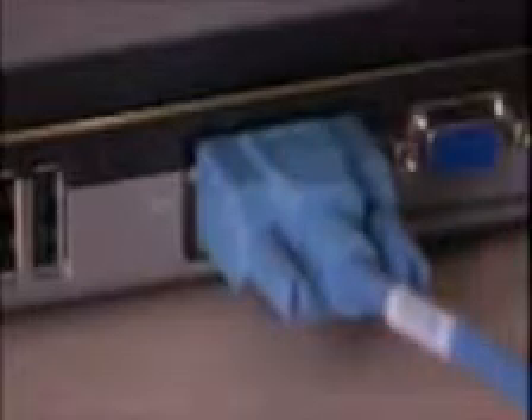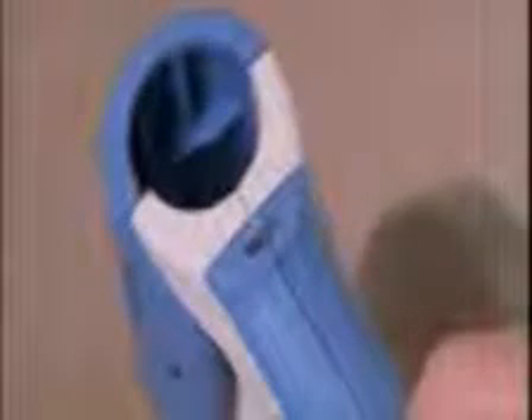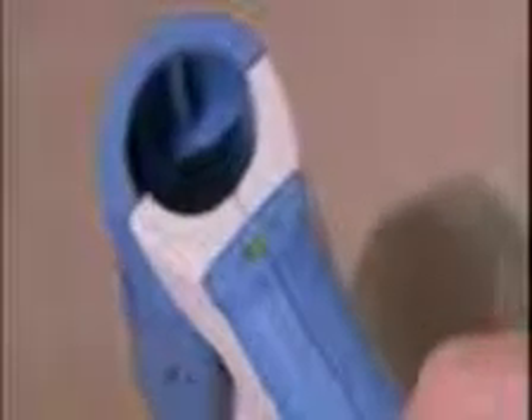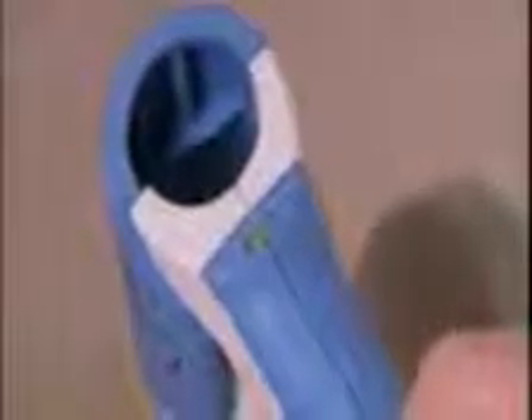The iQ Spiro must be calibrated using an iQ Spiro disposable mouthpiece. To load a mouthpiece into the device, line the pins of the mouthpiece up with the ports of the spirometer and press the mouthpiece in place. Next, close and latch the spirometer door. To set up the spirometer for calibration, connect the USB or serial cable of the device into the computer and check to see that the green light is on, indicating the device has power.